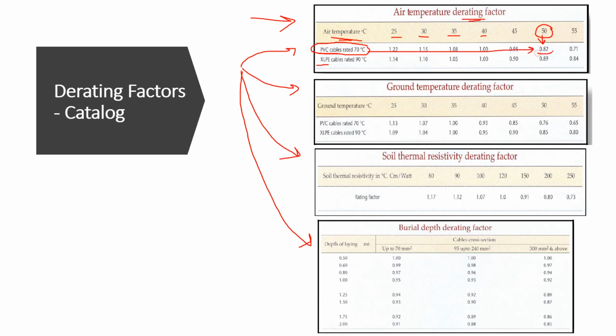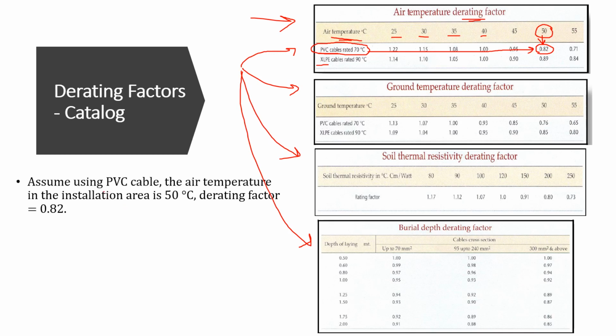So this value is the derating factor of our cable, 0.82. I'm going to take this value since it is the one which we need. Assuming we are using PVC cable and the air temperature in the installation area is 50 Celsius degrees, then the derating factor from the table will be 0.82.